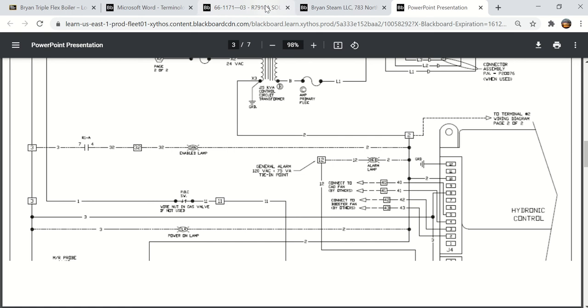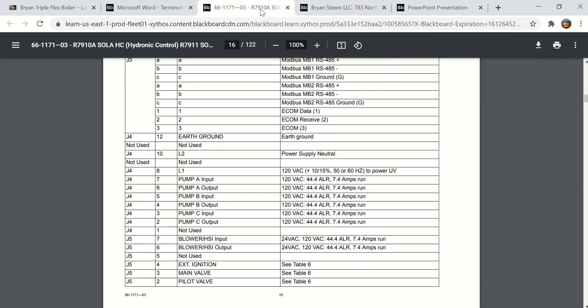So let's go back to the Honeywell page for those terminals. And you'll see here that J42 and J43 is called pump C input output, and J45 and 4 are pump B input output. Actually, what that is, is a dry contact that typically would be used to turn a pump on and off. When they say input and output, I don't know that you can really call one side the input, one side the output, but they're doing that.